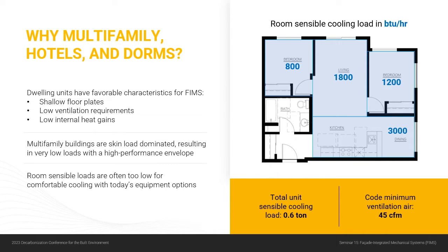These are the sensible cooling loads in the space. A typical bedroom might be 800, 1,000 BTUs. Another space with higher loads, like a dining room with a kitchen with some internal gains in there, might be somewhere around 3,000 BTU. But these are very low loads, even lower than typically you can get off-the-shelf equipment for. So looking at this two-bedroom apartment, your total load is only barely over half a ton, and you only need about 45 CFM of ventilation air.